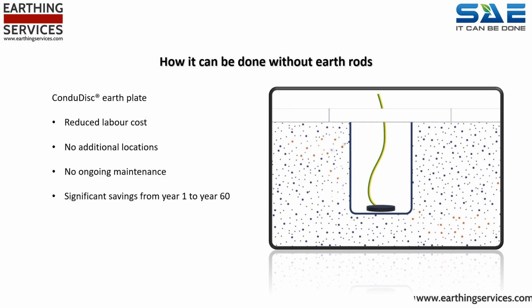This product is a far safer prospect to use and install than earth rods and encased copper plates. Increasingly, our clients are simply replacing earth rods with ConduDisc in their earthing system. The product is deterioration proof, reduces labour cost, requires no additional locations, requires no ongoing maintenance, and affords significant savings from year 1 to year 60.